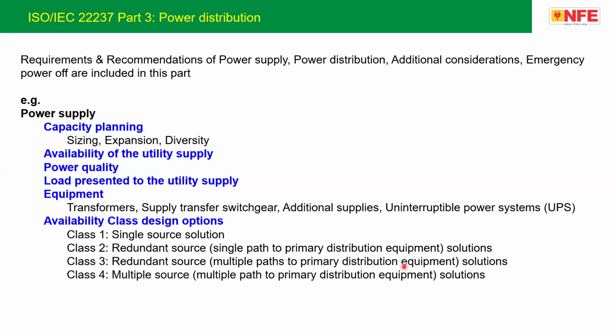Yes, sir. So the standard explains very well the requirement of availability class, which is required for the facility and the infrastructure. To meet that requirement of availability, the power supply and distribution within the data center shall be designed and selected in order to provide the required availability of the power supply to the end equipment. The end equipment is actually the rack. The availability class of the power supply and distribution shall be at least equal to that required by the availability class of the overall data center.